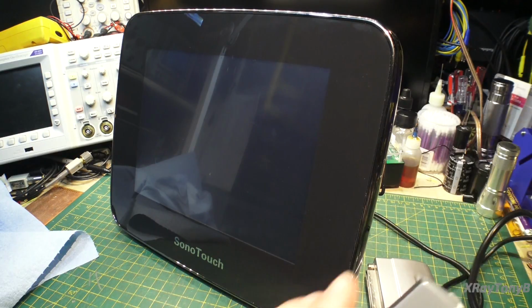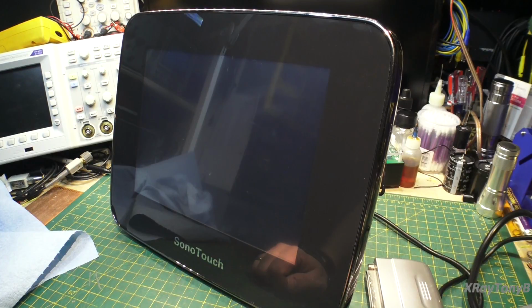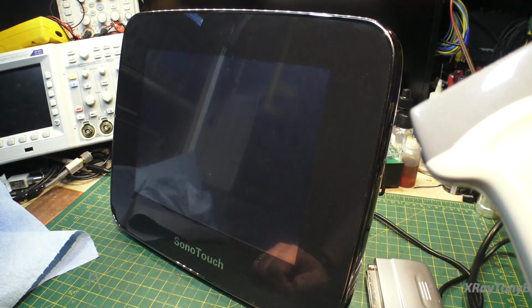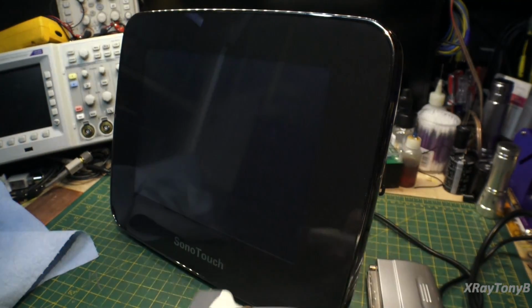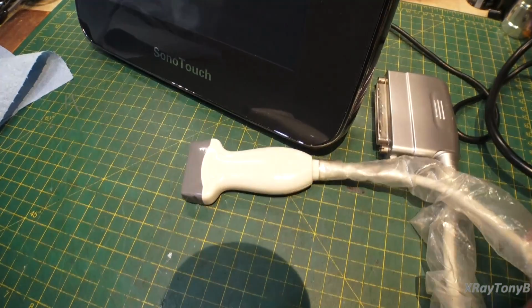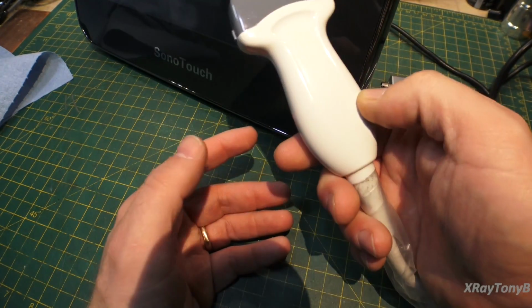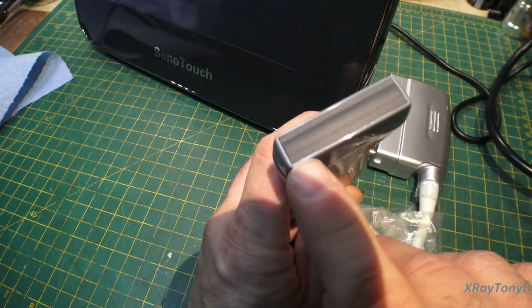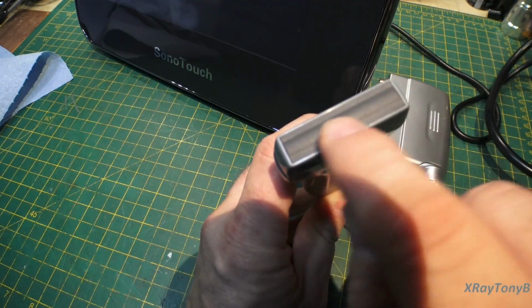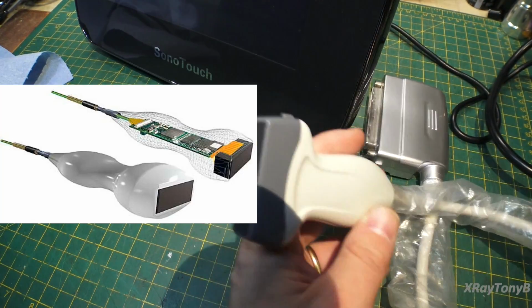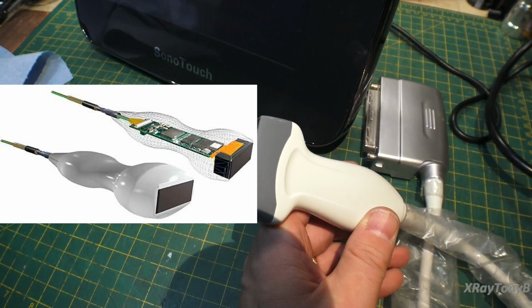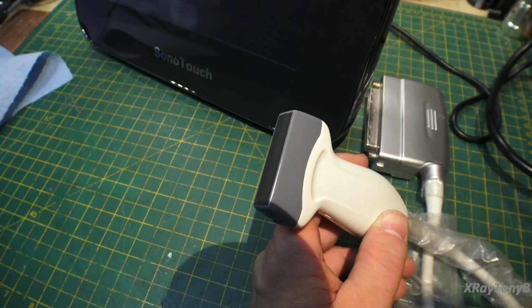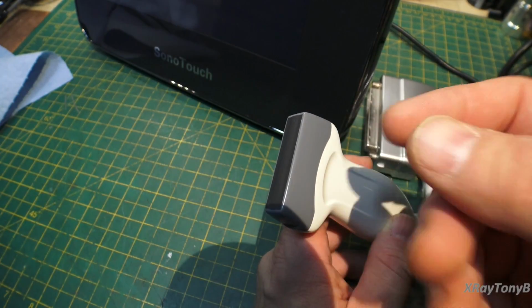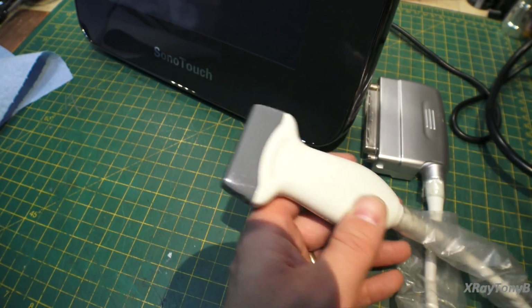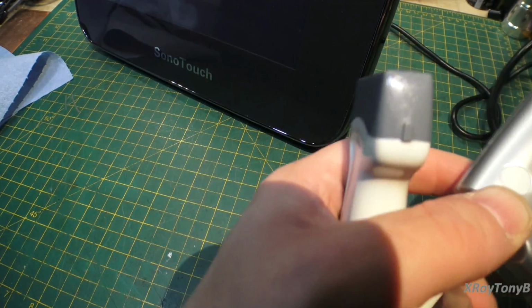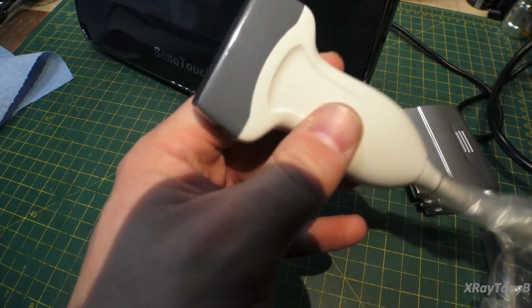But these sound waves are much higher frequency than our ears can hear. They're in the radio frequency range, but that's not radio frequency. As a matter of fact, here is a transducer. This would be an ultrasonic transducer. And you can see the ultrasound would actually propagate out of this little window. We call this the window. And inside here is a piezoelectric crystal. And the piezoelectric effect is when we apply a certain voltage to that crystal, we can make it vibrate. And we vibrate it at a very high frequency. This one in particular vibrates at up to 7.5 megahertz.